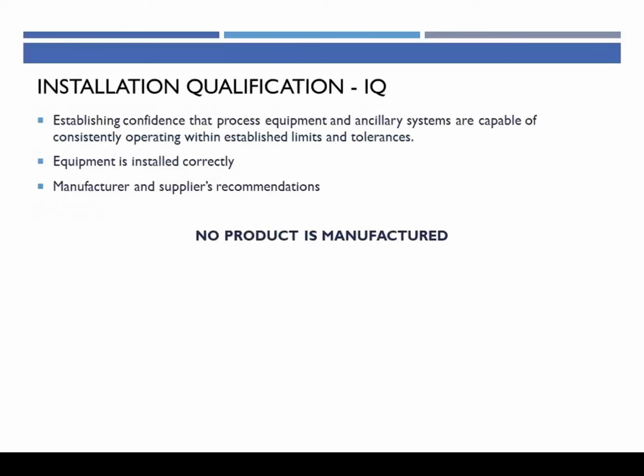All right, now let's dig into the IQ, the installation qualification. This is the first step, and it's all about establishing confidence that your process equipment and ancillary systems are capable of consistently operating within established limits and tolerances. You're going to have to describe what those conditions are and what those established limits are. You want to prove that the equipment is installed properly and you're following the recommendations of the supplier of that equipment.